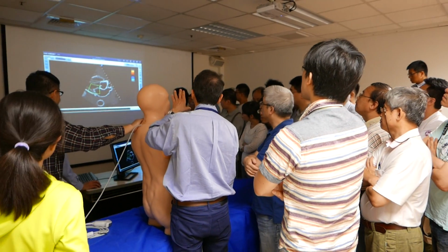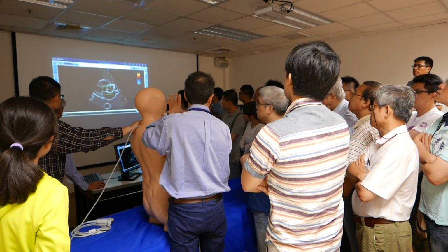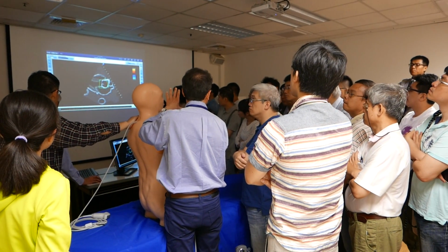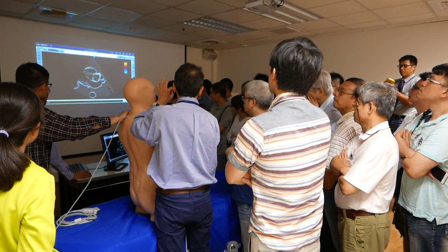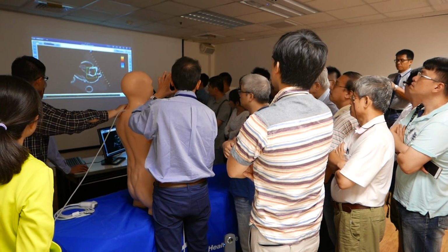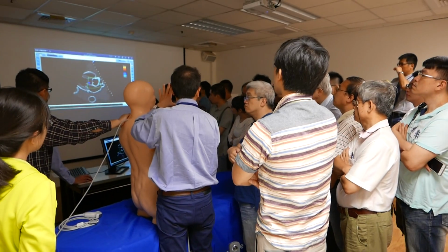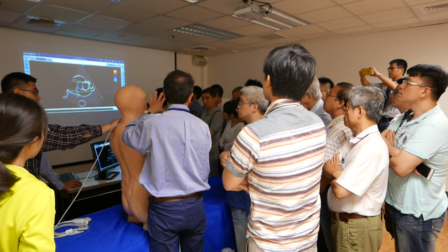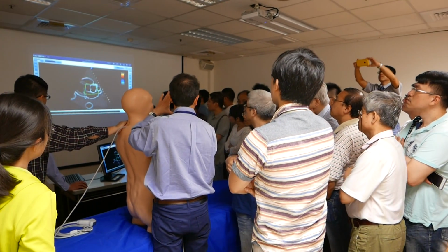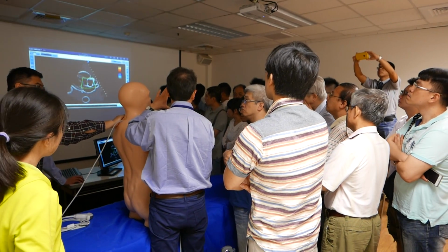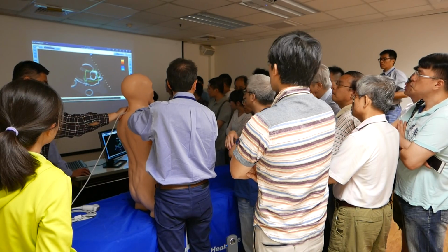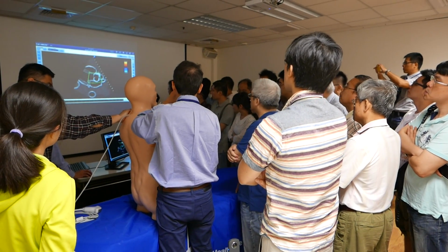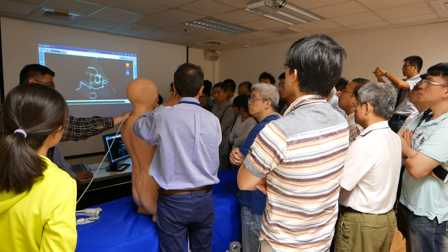So if you have 50 images per second with the 2D, you have a very nice fluent motion of the heart. When you start the color Doppler, the number of frames per second drops from 50 to 25 maybe. The larger your color window, the more severe the drop in the frame rate. Okay?